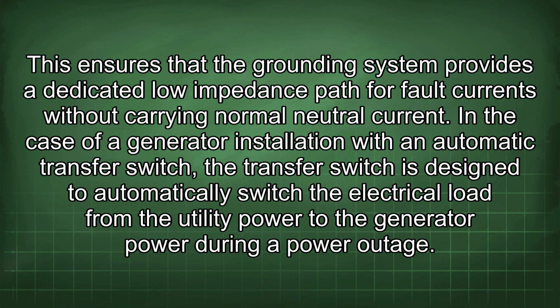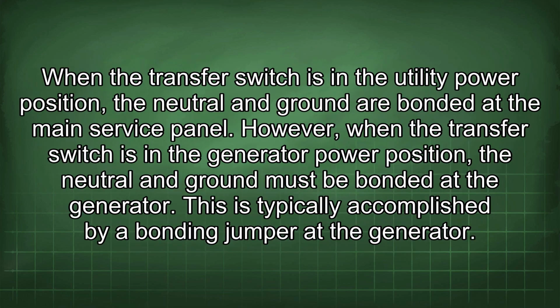In the case of a generator installation with an automatic transfer switch, the transfer switch is designed to automatically switch the electrical load from the utility power to the generator power during a power outage. When the transfer switch is in the utility power position, the neutral and ground are bonded at the main service panel. However, when the transfer switch is in the generator power position, the neutral and ground must be bonded at the generator. This is typically accomplished by a bonding jumper at the generator.